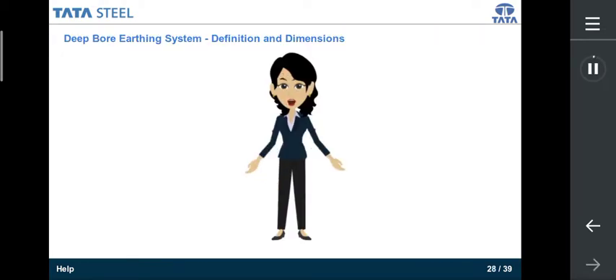In the previous topics, we have learned about two types of earthing pits, pipe earthing pit and plate earthing pit. In this topic, we shall learn about another type, which is the deep bore earthing pit. You know that earth pits are made to test earth electrode resistance and to find out the suitability of the area for earthing. When the testing is done, the required earth electrode resistance should be less than 1 ohm.